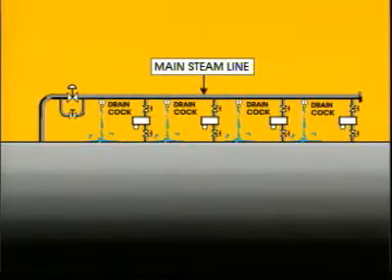It can take several hours to heat the line, so be patient. Do not rush. Close the drain cocks one by one when steam is coming through them.